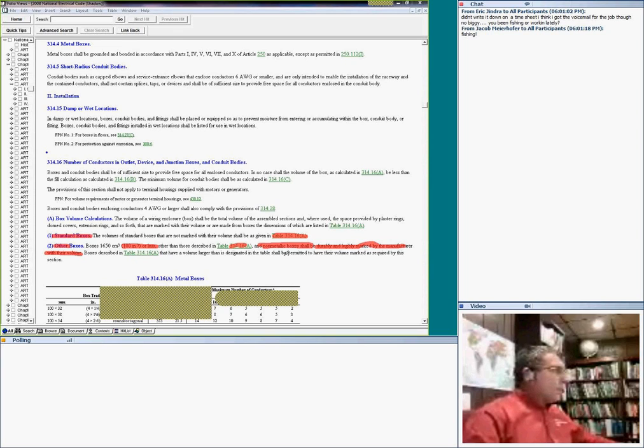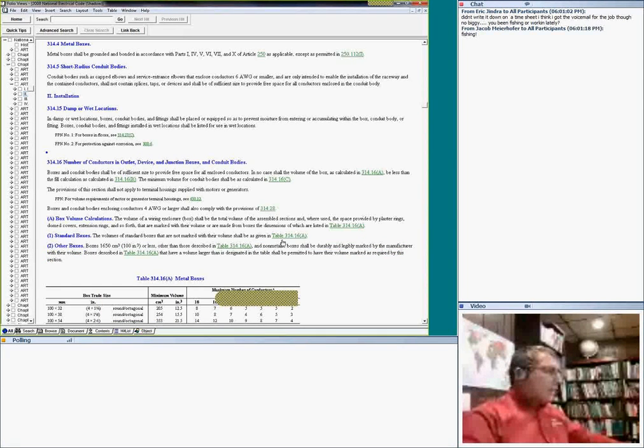The non-metallic boxes shall be durably and legibly marked by the manufacturer with the volume of the box. If boxes are larger than the table, their volume must be marked as required by this section. But the most important thing I'm going to mention is that non-metallic boxes have to be marked by the manufacturer with how much they fit, how many conductors they can fit. So very important. The metallic boxes are right in here.